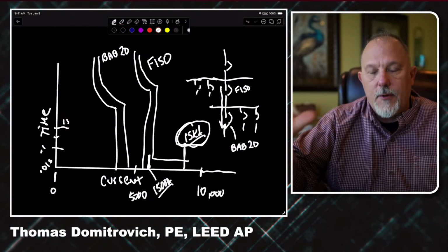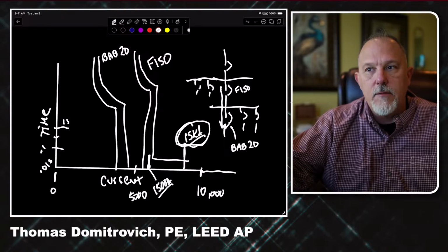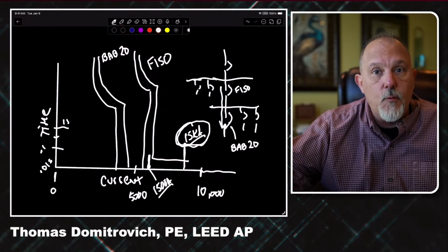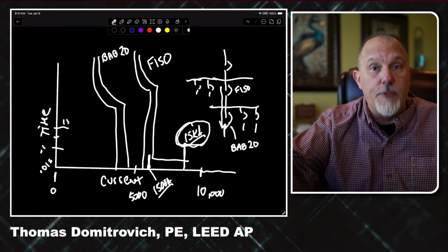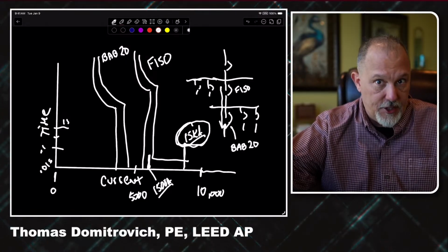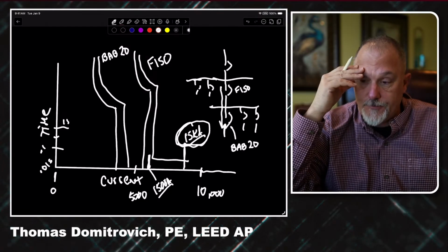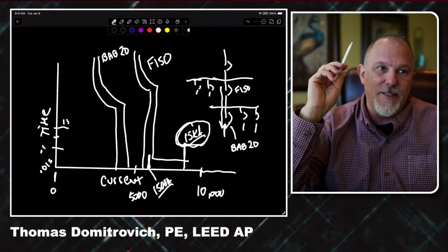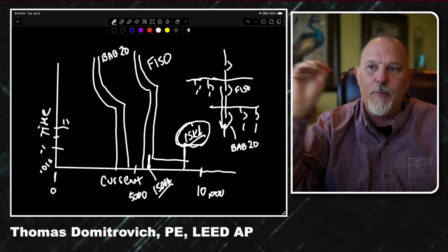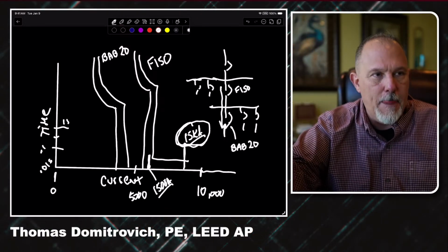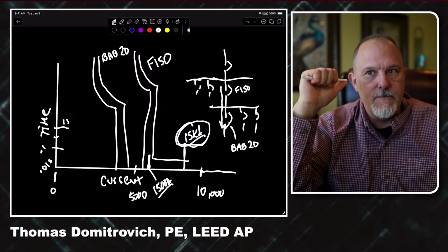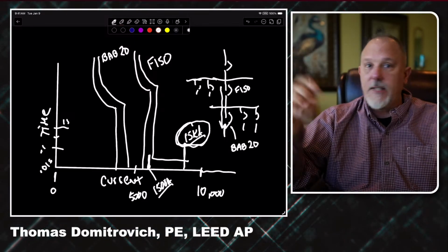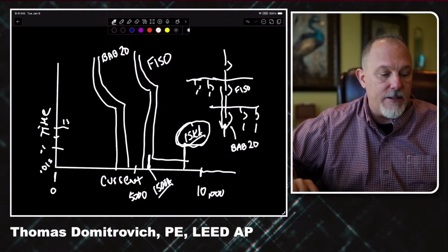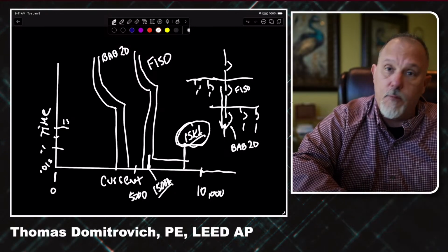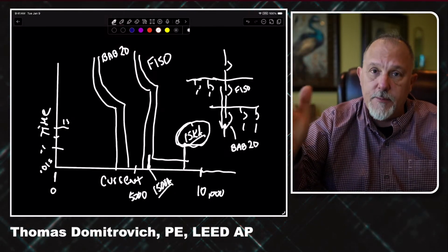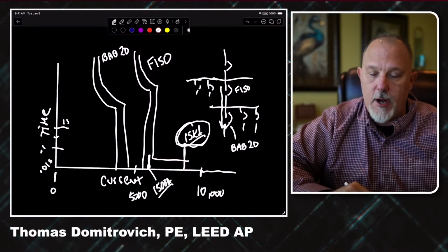So then I'll argue it, or I won't argue. I'll say, well, what about another current value? What current value would you want to coordinate to? I was with the chair of a committee at one point. I won't say his name. We had breakfast. And I said, all right, because this is what we're arguing about, is that pickup point, whether you coordinate to the three-phase bolted fault current value or not.